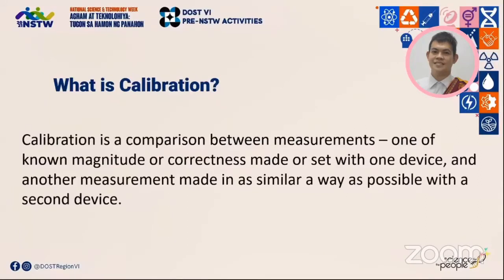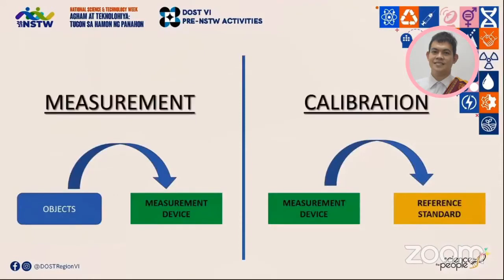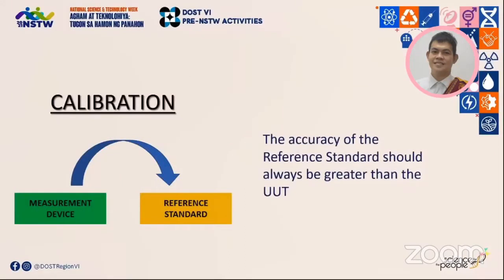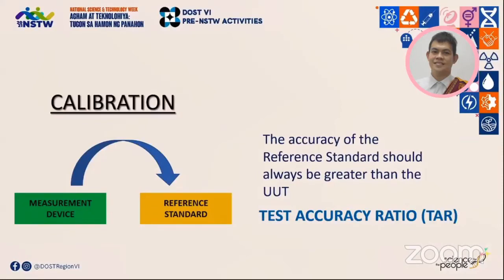Both measurement and calibration are similar in the sense that they both involve a comparison using a measurement device. Their difference lies in the comparison being done. Measurement involves the comparison between an object and a measurement device, while in calibration, it is your measurement device that is compared to a reference standard. When a device is being calibrated, the reference standard must be better in terms of accuracy compared to the unit under test. This is known as the test accuracy ratio or TAR. Typically, the accuracy of the standard should be 10 times the accuracy of the measuring device being tested; however, a ratio of 3 to 1 is acceptable by most standards organizations.